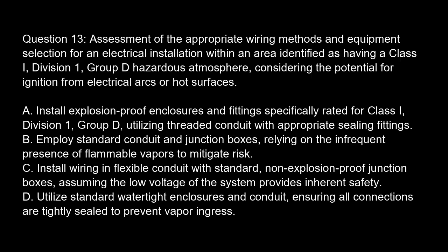Option B. Employ standard conduit and junction boxes, relying on the infrequent presence of flammable vapors to mitigate risk. Option C. Install wiring in flexible conduit with standard non-explosion-proof junction boxes, assuming the low voltage of the system provides inherent safety. Option D. Utilize standard watertight enclosures and conduit, ensuring all connections are tightly sealed to prevent vapor ingress.